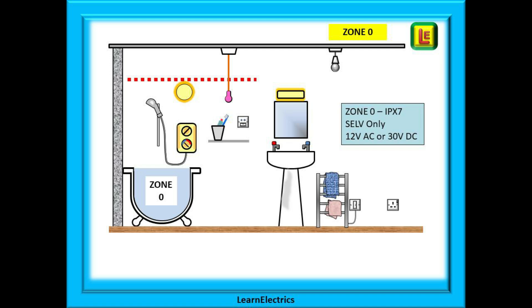Zone 0 is the space inside the bathtub — the space where the water is, up to the top of the bath; in other words, where you will be sat when you have a bath. Anything electrical in this zone must be IPX7 rated (submersible) and the voltage must not exceed 12 volts AC or 30 volts DC. It must be a SELV circuit only, and any 230 volt transformers used to supply this separated extra low voltage must be installed outside the bathroom zones, with only the ELV cables installed in the zones.